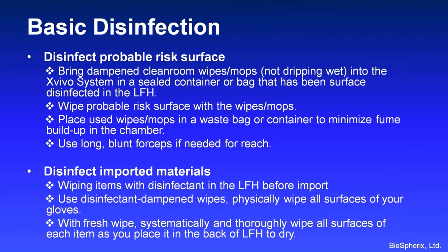Then how to do it? For wiping the probable risk surfaces, you need to bring a damp clean room wipe or mops, not in a dripping wet way, into the Xvivo system in a sealed container or bag that has been surface disinfected in a laminar flow hood. Wipe probable risk surfaces with the wipes or mops. Place those used ones in the waste bags or container to minimize fume buildup in the chamber. Use long, blunt forceps if needed for reach.